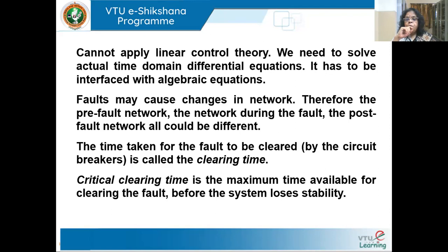And there is one time beyond which you cannot let the fault persist. That means if you do not clear the fault before that specific time, the system will become unstable. That time is called the critical clearing time. So what is the critical clearing time? The maximum time available to clear the fault.